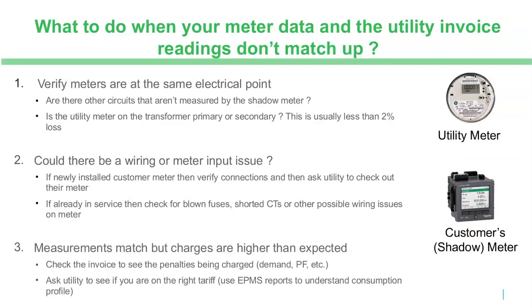Secondly, could there be a wiring issue either with your meter or with the utility's meter? Usually those things show themselves pretty early on. You'll install your meter, you'll see a big difference with the utility meter, and you'll find out a problem exists. And once it's corrected, you may be able to yield some savings moving forward, but certainly you may be due some refunds going backward.